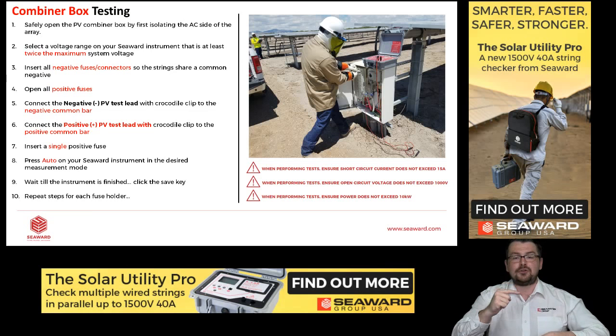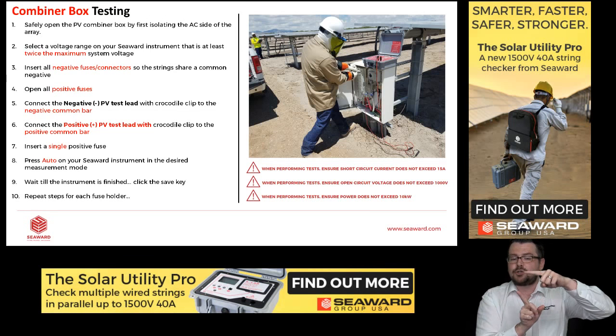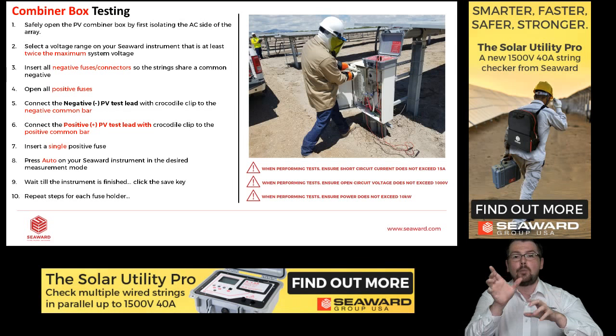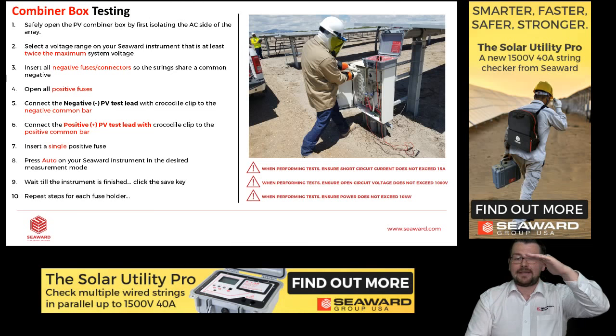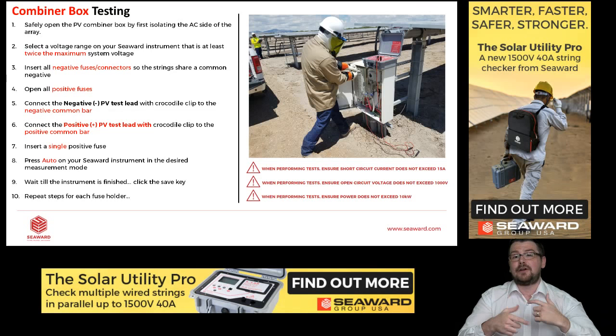In each of those fuses will either be a single string, or perhaps, as I mentioned earlier, several strings in parallel. So what we need to do as an engineer is test each of those individual strings if we can. What we don't want to do is test all of them at one time, because that means they'll all be in parallel and we'll have a very high current rating, and this will damage your machine. So we've devised a method which can very quickly and easily test inside of a combiner box.